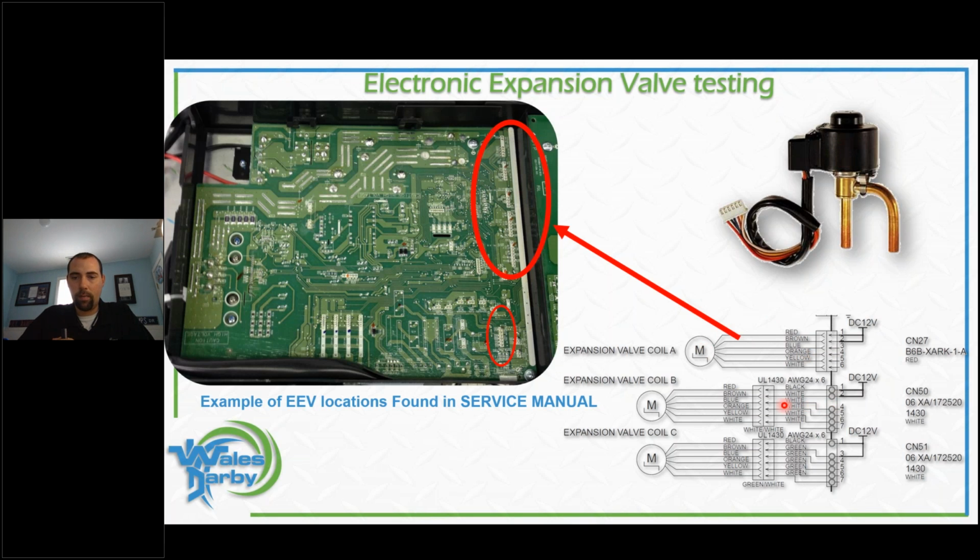If you notice these, I have a Molex plug. That's what this is telling us. We got a Molex plug in between the board and the valve. So these are shorter harnesses. So if I had an A valve, a 5 and a 6, I can potentially replace almost everything out there in the field. So it's not a bad way to deal with it, especially if I had maybe a multi-zone system and one valve's bad. If I have an empty port, I have the potential to use that as an extra part, maybe to fix it for the night until I can get an additional valve installed. So just a little tip there.